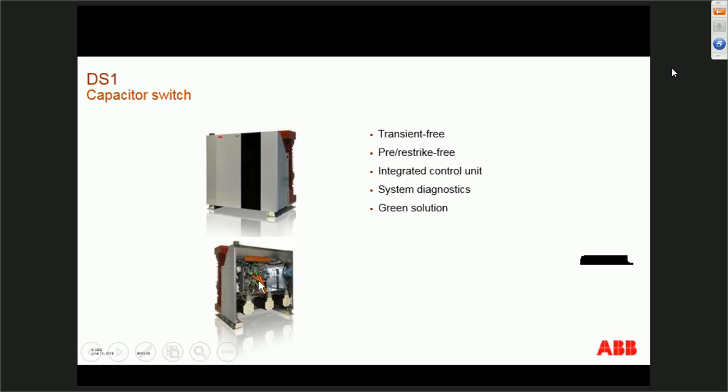There is the ACU, which is the onboard computer that has full diagnostic testing of the motors. The motors constantly do what we call a little jiggle test, where it will literally feel if there are any torque changes within the control system of the device itself. So it knows that something's going to go wrong before it goes wrong, because it measures the torque during its opening and closing operations. If that torque goes outside of a predefined range, high or low, it can tell the ACU that something is either wearing out or breaking. This is translated out to a dry output contact, similar to what you see in the magnetic actuated technology breaker. So we have a status that says something is going wrong, please do maintenance.